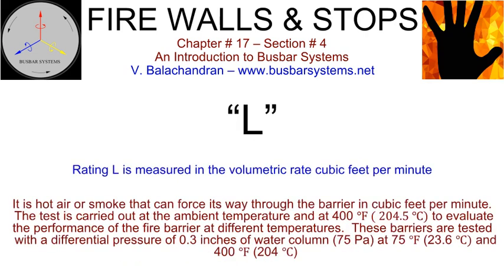Rating L is measured in cubic feet per minute. It is a volumetric rate of hot air or smoke that can force its way through the barrier in cubic feet per minute. The test is carried out at the ambient temperature and at 400 degrees Fahrenheit or 204.5 degrees Celsius to evaluate the performance of the fire barrier at different temperatures. These barriers are tested with a differential pressure of 0.3 inches of water column or 75 Pascal at 75 degrees Fahrenheit or 23.6 degrees Celsius and 400 degrees Fahrenheit or 204 degrees Celsius.